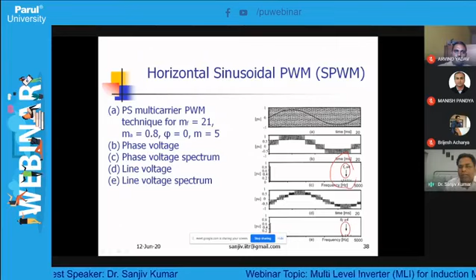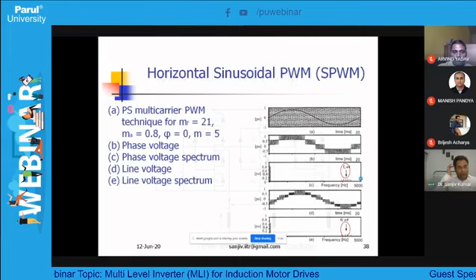Now look at the performance for phase shifted. As of now the harmonics lie either at the FC or at a sideband of the FC, but here the harmonics lie at 4 times the FC, that is 1050 multiplied by 4, 4200. You can see, so your filter size is very much reduced. That is the advantage of this phase shifted carrier wave modulation.